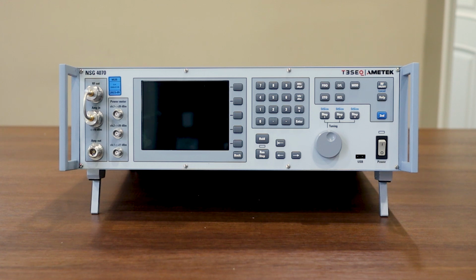The Teseq NSG4070 model we're going to be using for today's video is the Teseq NSG4070 C2-80 model, which is mainly used for IEC 61000-4-6 testing, as it has an 80 watt built-in amplifier from 150 kilohertz to 230 megahertz. Regardless of the amplifiers that are built into the 4070 itself, all the systems will have an integrated signal generator with a frequency of 4 kilohertz to 1 gigahertz and 3 power meter inputs with the same frequency range of 4 kilohertz to 1 gigahertz.